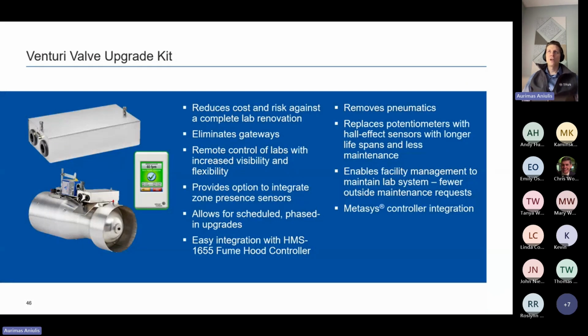Finally, we have a Venturi valve upgrade kit. This is geared for old Venturis where the cone spring assembly and the valve body is good and it's still doing what it's supposed to do. But the actuator is pneumatic, the controls are legacy, and they're not integrating with your building automation. And you have a space where you don't want to do a capital expense and introduce new valves. So you can use an upgrade kit, which comes out of your maintenance budget. So you can just do an in-field retrofit without needing to get into the ductwork.